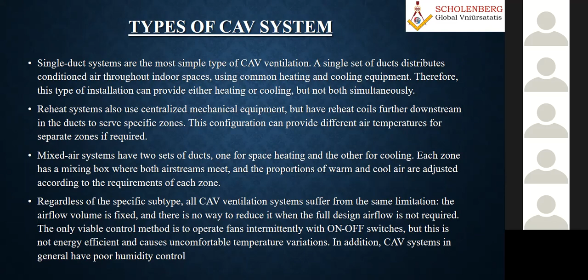Whatever the specific type, all constant air volume systems suffer from the same limitation: the airflow volume is fixed. Whether I fix 100 CFM or 200 CFM or 300 CFM, it is fixed, and there is no way to reduce it when the full design airflow is not required. So the only viable control method is to operate fans intermittently with an on-off switch, but this is not energy efficient and causes uncomfortable temperature variations. In addition, CAV systems in general have poor humidity control because everything depends on the dehumidification coil.